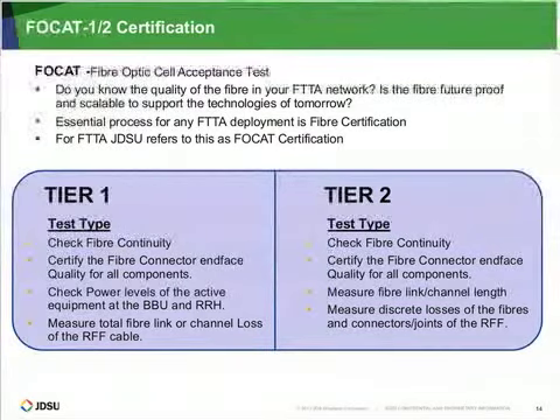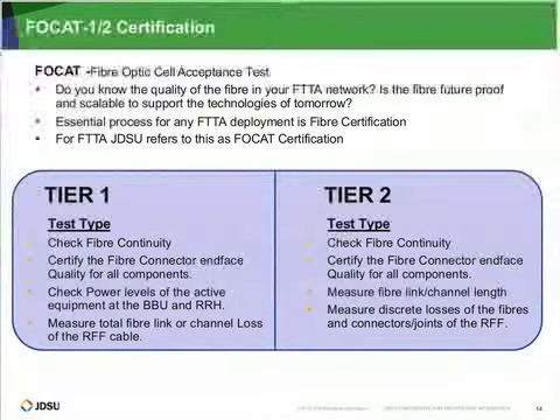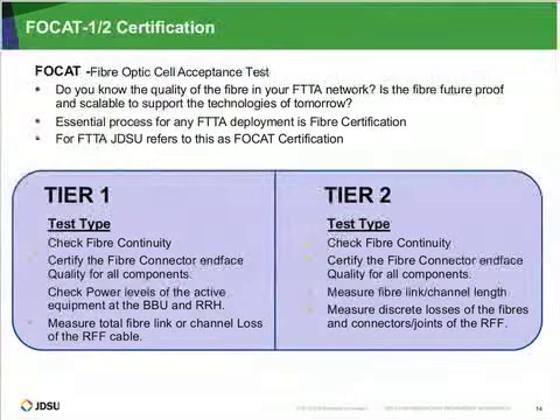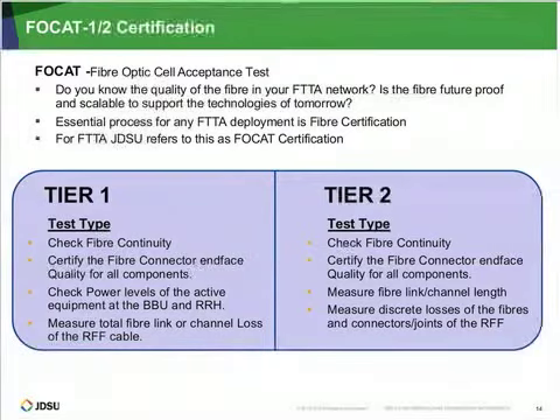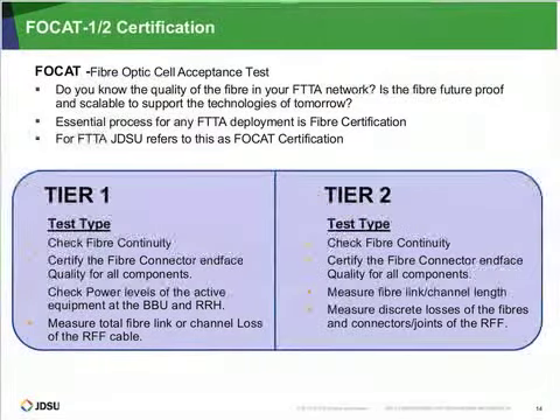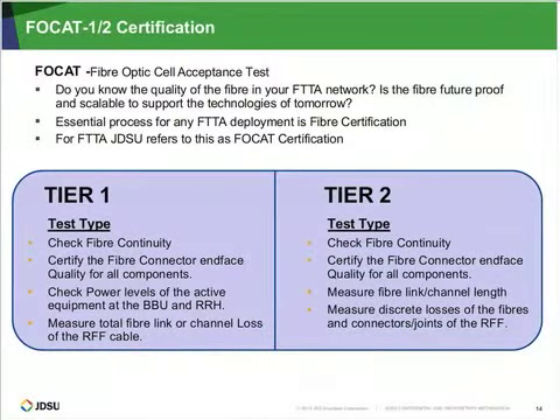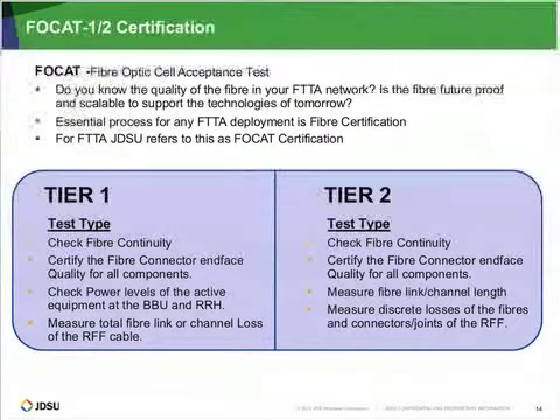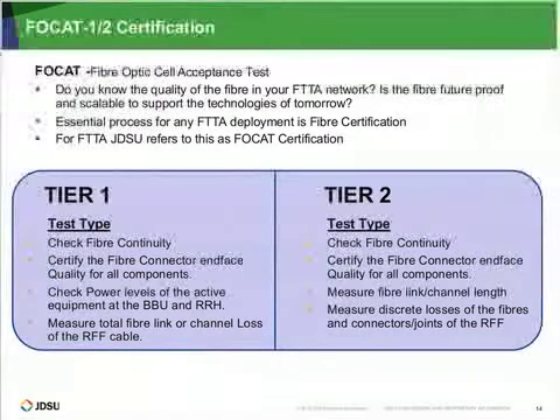The Tier 2 test includes an OTDR, a more sophisticated tool. The first thing to do is check the fiber continuity again. Most importantly, and most vulnerably, check the connector end faces and certify those. Then with the OTDR you can measure the length of the fiber, which you should know exactly. If you have a different length, then you have a break somewhere. The OTDR can also measure the discrete losses of all the individual lengths of fiber, and all the connectors or joints up and down the tower. It's more sophisticated equipment, and I'll show you some pictures in a couple of minutes.